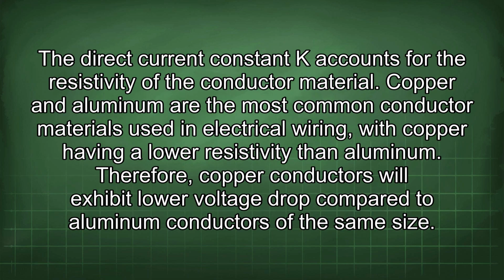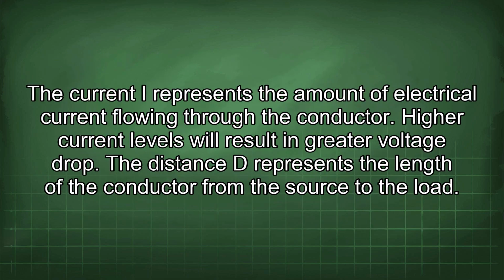The direct current constant K accounts for the resistivity of the conductor material. Copper and aluminum are the most common conductor materials used in electrical wiring, with copper having a lower resistivity than aluminum. Therefore, copper conductors will exhibit lower voltage drop compared to aluminum conductors of the same size. The current I represents the amount of electrical current flowing through the conductor. Higher current levels will result in greater voltage drop.